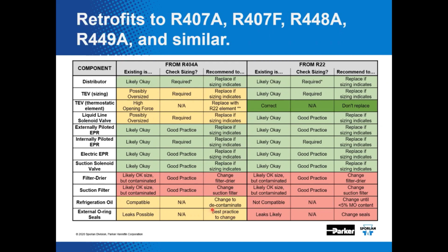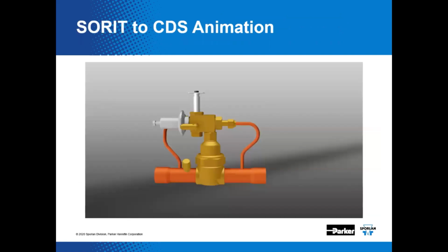Now you notice we've got some yellow and red down here. When it comes to filters, oil, and external seals, red means probably not okay. Yep. It's important that the system be leak tight, clean, and dry, and that's a benefit to everybody. It'll make for a much more reliable system, a better performing system, and a more energy efficient system.